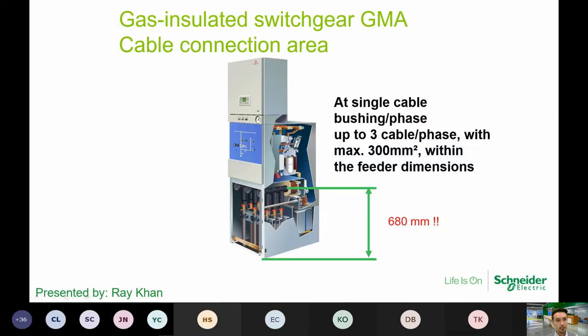Okay. Apart from this, from the cable compartment, the cable connection area, having a larger space is actually much better. The reason why is because it's much more convenient for the cable jointers. All right. So a single cable bushing can cater up to three cables, or three phase cable. But the maximum dimension is about 300 mm squared. All right, so by catering a space of 680, it gives the cable jointers much more room to do a proper termination, which is actually much safer at the end of the day.